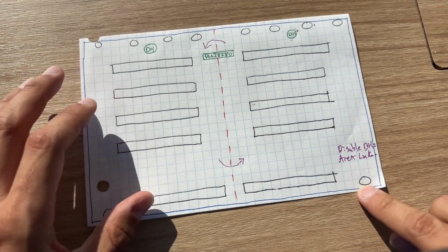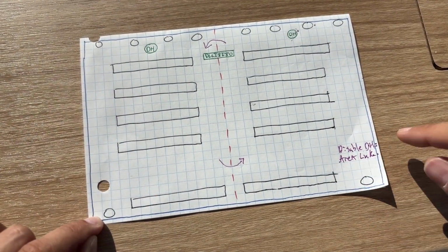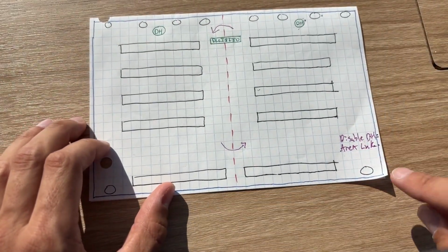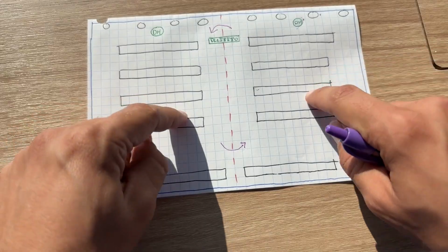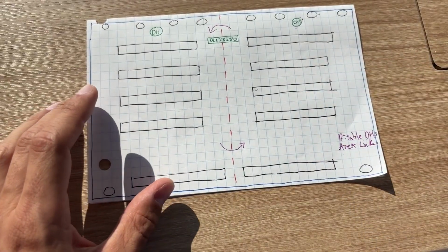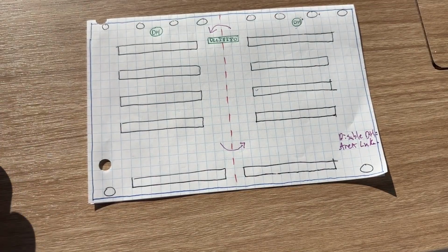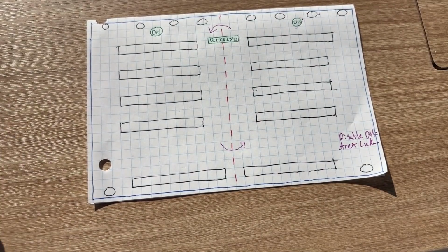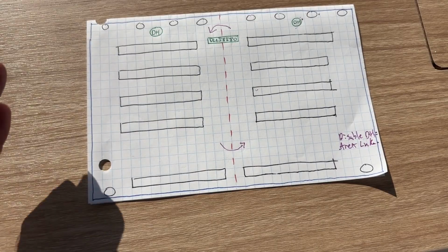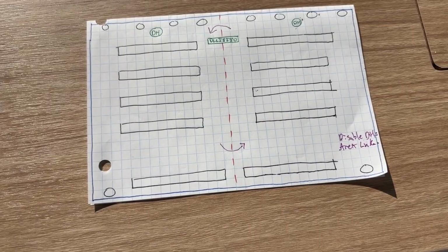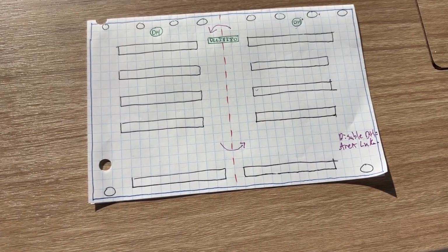And the magic behind this is I'm using a base link area, you see here in blue, that encapsulates both areas. And when I send a command to the base link area, it will transmit to the 2 areas within it. The unique challenge here is that if I link both areas together without doing anything else, the 2 daylight regulating sensors will conflict with one another. So what I do is I strategically choose the sensor with the most daylight and disable the other one when the rooms are open and need to be controlled together.